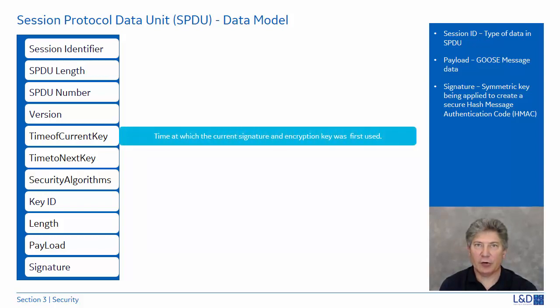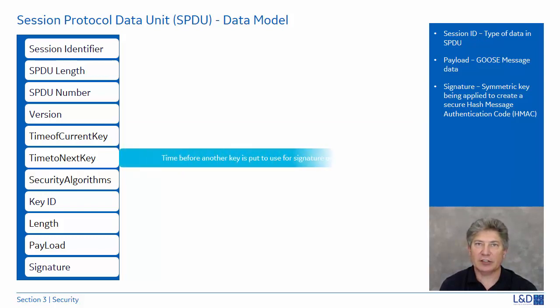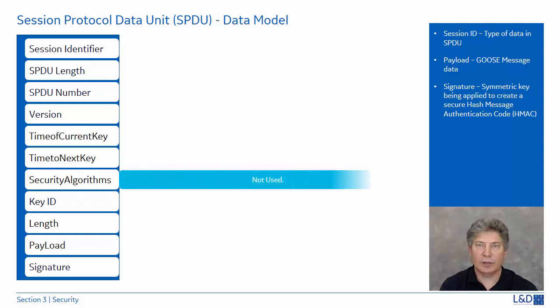The time of current key is a security attribute which represents the time at which the current signature and encryption key was first used. Time to next key is a security attribute that represents the time before another key is put into use for signature and encryption. It is recommended that the key distribution center changes the symmetric keys used for signatures and encryption at least every 48 hours. The value is specified in minutes. A minimum time to next key is expected to be 30 minutes. This value should be used for updates of the keys in situations where the current key has been compromised. Security algorithms is not used.